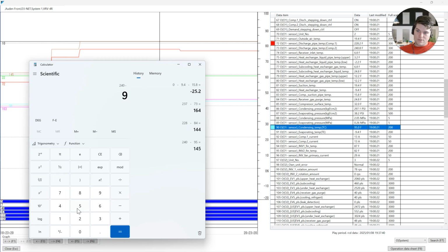So we're going to use 240 minus 95. That is 145 degrees discharge superheat. Now, what's the range? 32 to 72. Is this above 72? If you don't know the answer to this, then please stop watching this video. It's 145 degrees. That is crazy high. That is an insane amount of discharge superheat. It's like we're going to the moon and you're not stopping us.